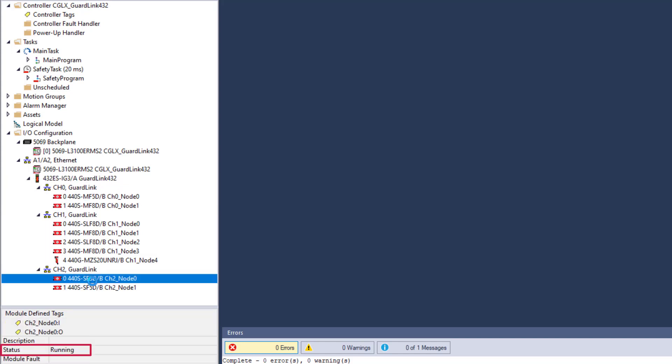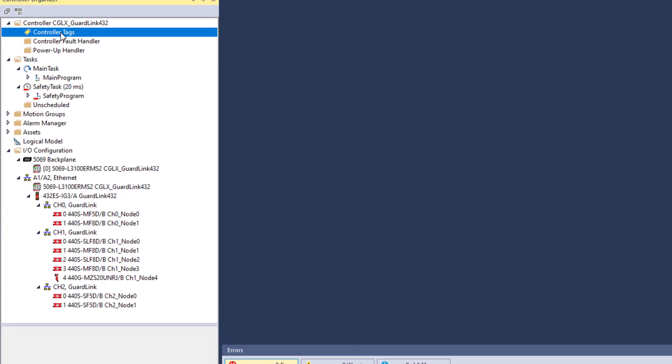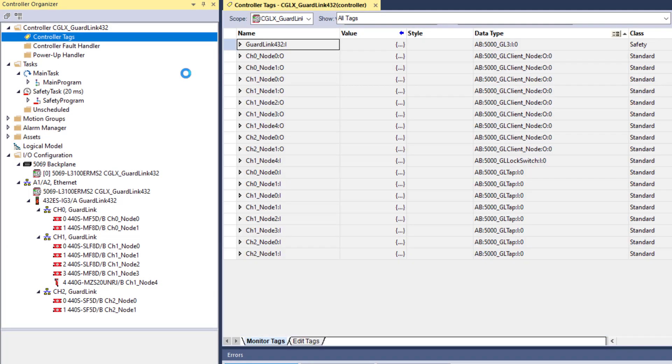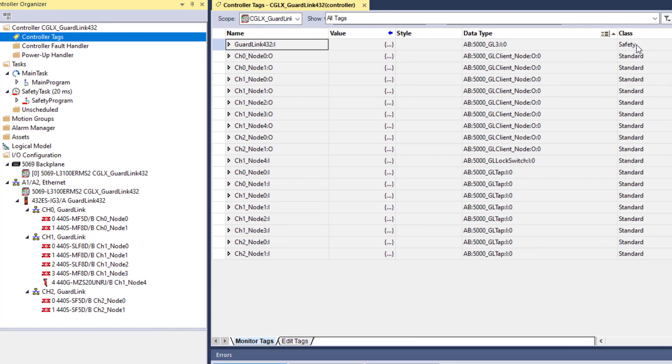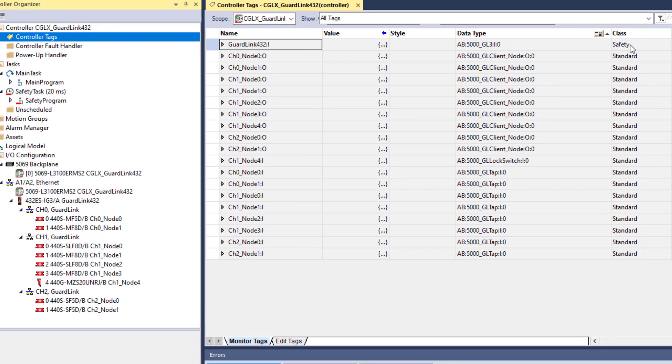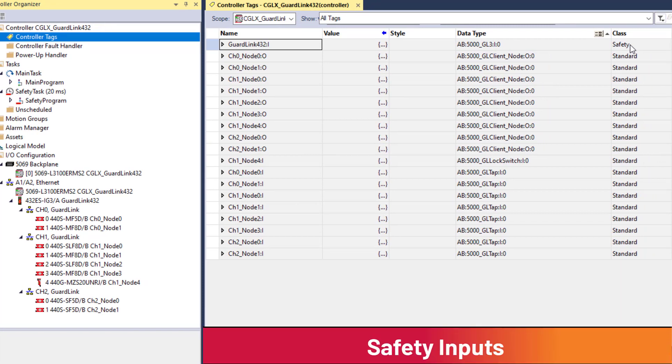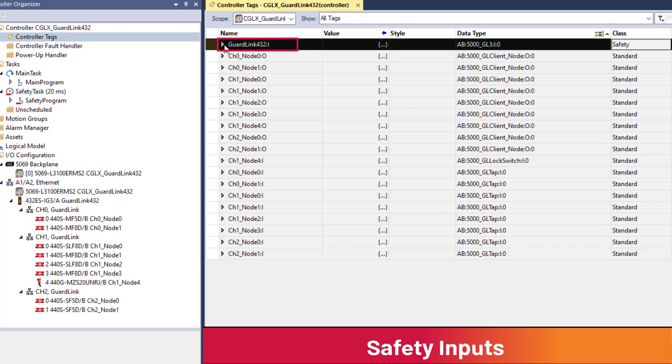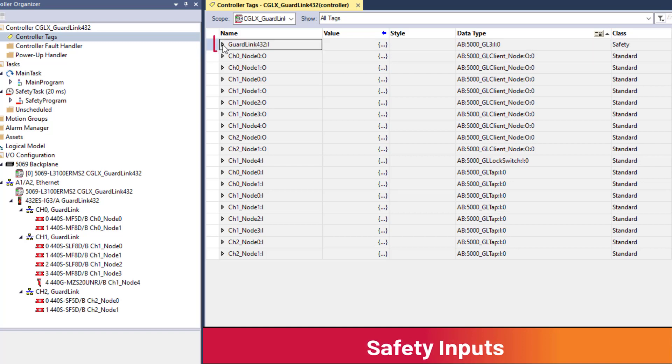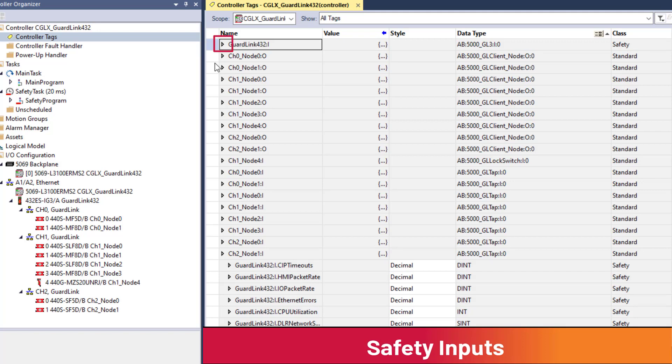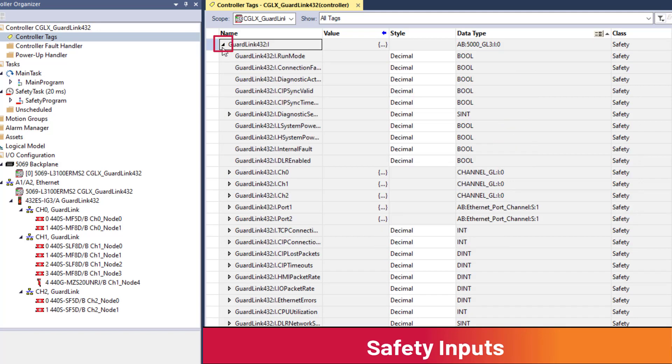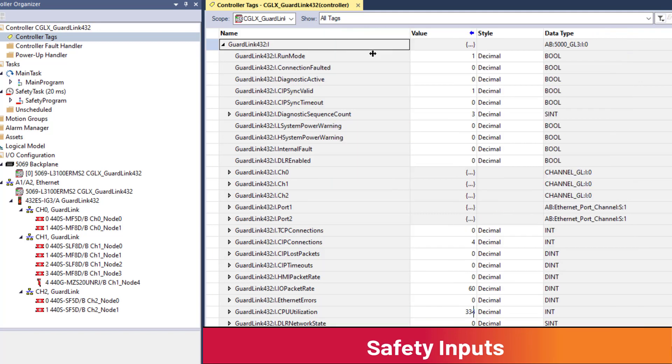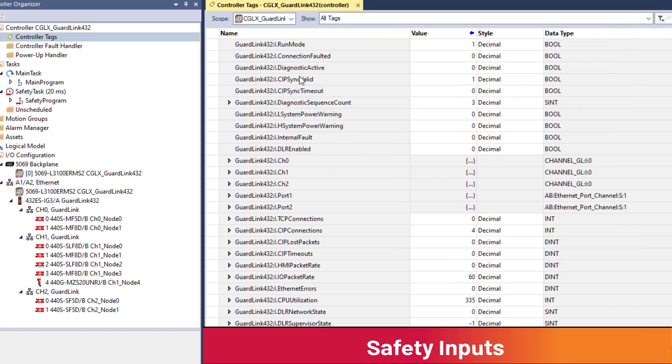Double-click controller tags to see the inputs and outputs the GuardLink interface provides. First, let's monitor the safety inputs. Looking down the class column, the GuardLink interface safety tag is designated with class equal to safety. There is one safety input tag structure per GuardLink interface. Clicking the arrow by the tag name expands the contents of the tag structure. The safety tag provides detailed diagnostic information for the GuardLink interface.